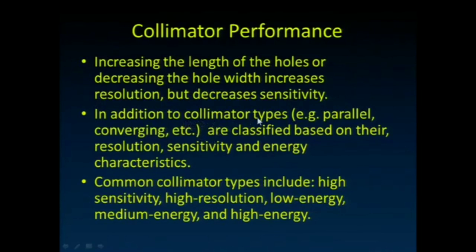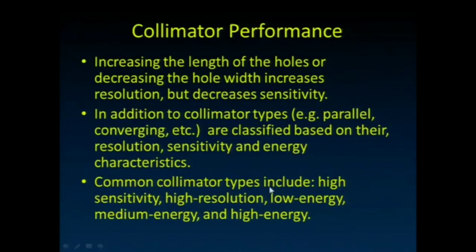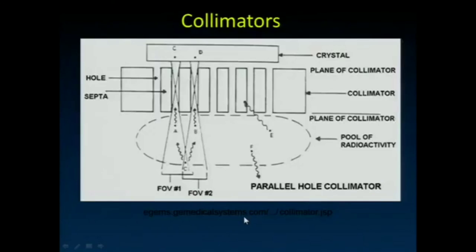In addition to collimator types — parallel hole, converging hole, pinhole — they are also classified based on their resolution, sensitivity, and energy characteristics. Common types include high sensitivity, high resolution, low energy, medium energy, and high energy collimators.